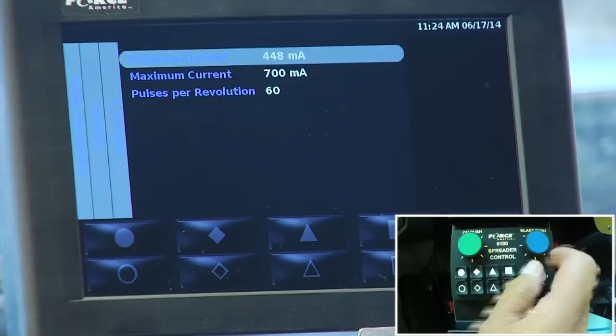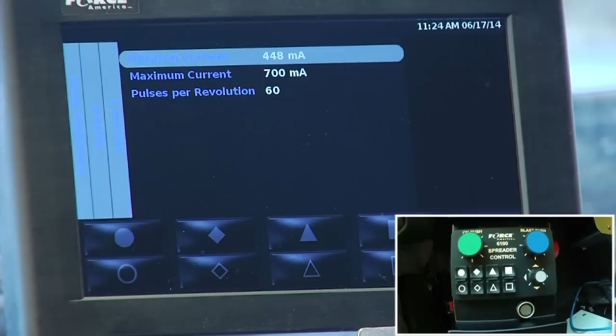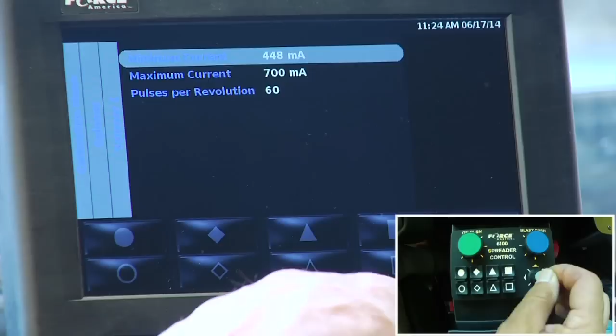All a spinner does for you is adjust a hydraulic valve for min and max. So when we have the spinner knob at 0, we don't want it to be creeping. So it's the same as we did the auger min and max, except we don't have feedback in a spinner, so you physically would need to look in the mirror and go into spinner min and run your output. So you would basically turn it on and run the spinner until it slows down to 0. So you would change these milliamps until the spinner almost stops, might just be creeping a little bit. That's your min, okay? Now your max, in my mind, really is up to you.